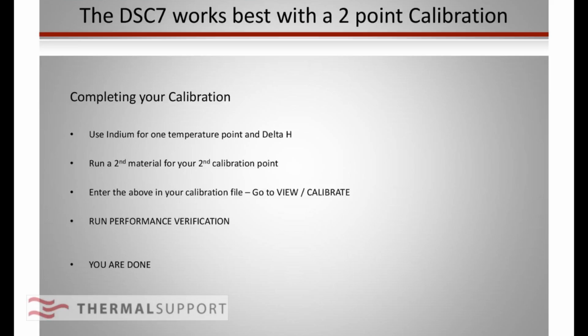If you want to get into that calibration file, you go to the top file menu bar under methods, and you say view calibrate. When you're done, run a performance verification. Indium is great under almost all circumstances, and you're done. And that's pretty much all they're doing. I left a lot of stuff out. I left out showing the software, where the assumption is that you're going to use quick help, and you understand that. I hadn't actually gone straight through the calibration routine as far as showing it on the software, but you can see it in QuickHelp. It's easy to find under the method.